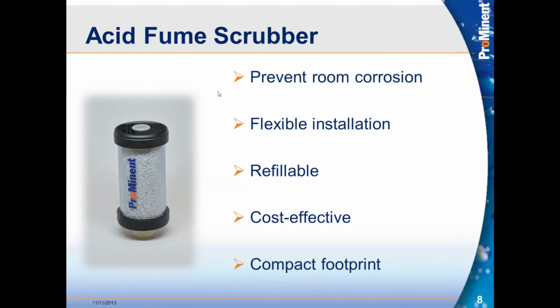Moving on, our acid fume scrubber is a new product that we released this year, and the concept behind the acid fume scrubber is to prevent equipment room corrosion that is associated so much with muriatic hydrochloric acid, with the fumes coming off those tanks. Quite frequently, and in most cases, these tanks that house the acid are not sealed. And you can't really seal a tank, because if you put a hose into a tank and you're pulling fluid out of that tank and you completely seal it without some way to equalize the pressure, you wind up collapsing that tank. And so the acid fume scrubber gives us a way to relieve, give an air break on that to equalize pressure in a way that's going to keep the fumes from escaping into the room, but also allow that tank to equalize.